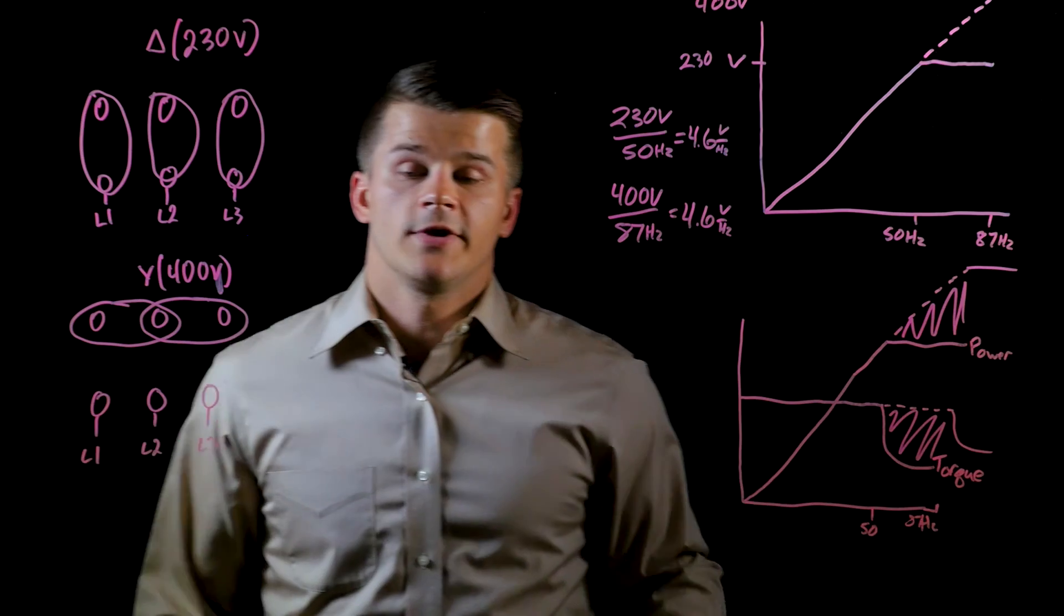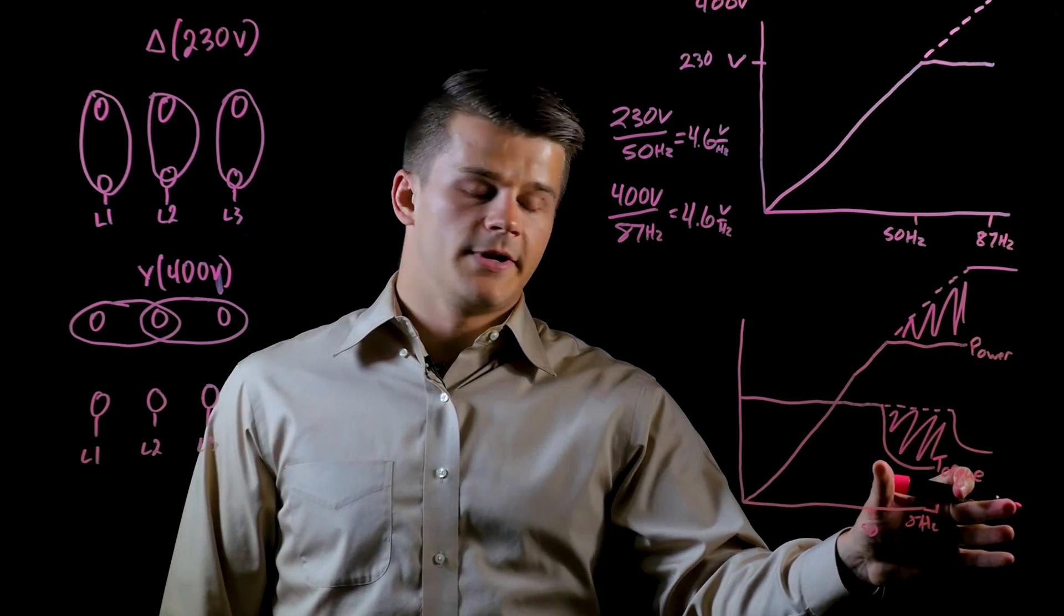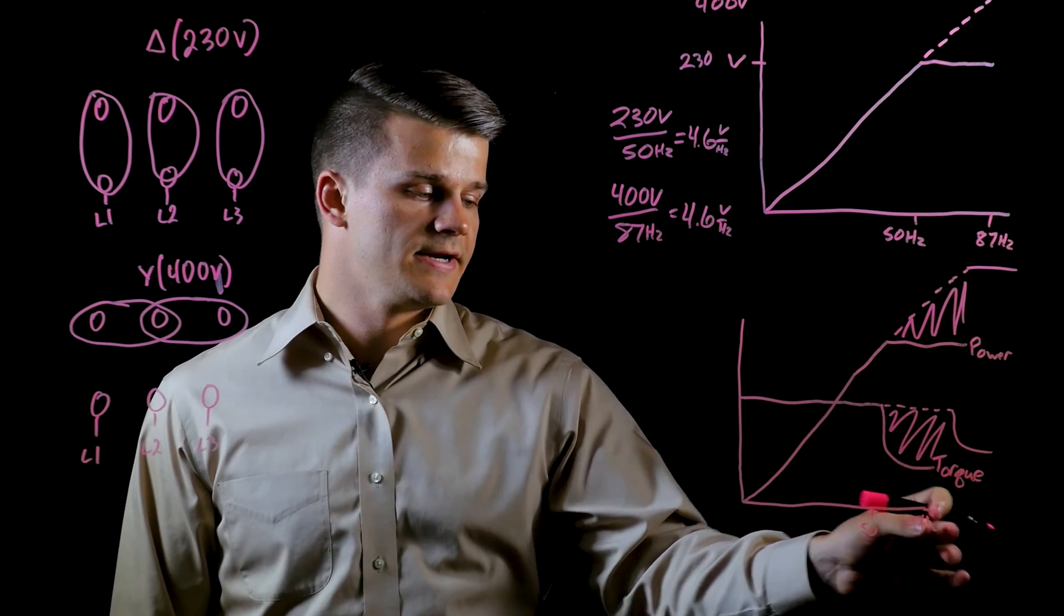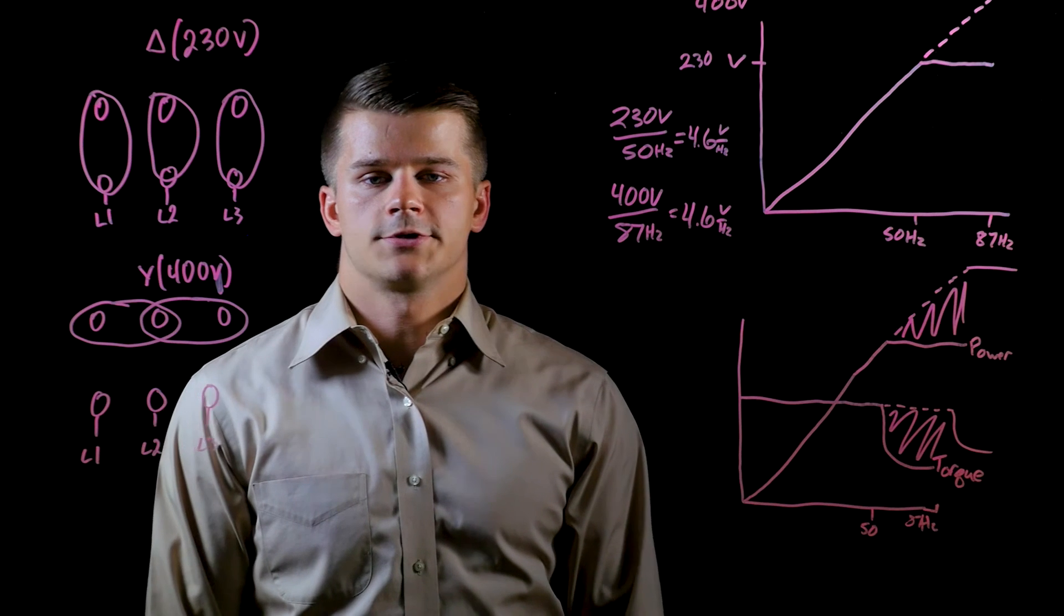Once we hit 87 Hertz, it would do the same behavior as previously. As you can see, we get this extra power and the torque maintains constant from 50 to 87 Hertz in the same IEC rated motor. And that's the 87 Hertz motor trick.